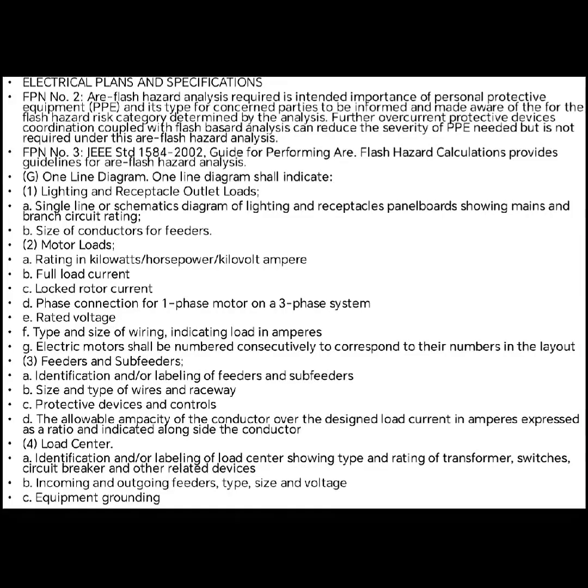Feeders and sub-feeders: identification and or labeling of feeders and sub-feeders, size and type of wires and raceway, protective devices and controls, the allowable ampacity of the conductor over the design load current in amperes expressed as a ratio and indicated alongside the conductor. Load center identification and or labeling of the load center, showing type and rating of transformers and switches, incoming and outgoing feeders, type, size and voltage, equipment grounding.